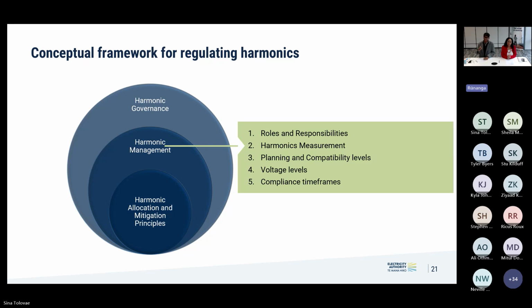The next key thing we'd like to discuss is harmonics measurement. Overseas, for the past two decades, they have had good measurements. It's mandatory in the code, which is why they have background measurements. So even before a new solar farm, BESS, or asset like a data center comes in, we can understand the existing harmonics, and only then see how a new asset will distort that harmonic, whether amplified or otherwise.